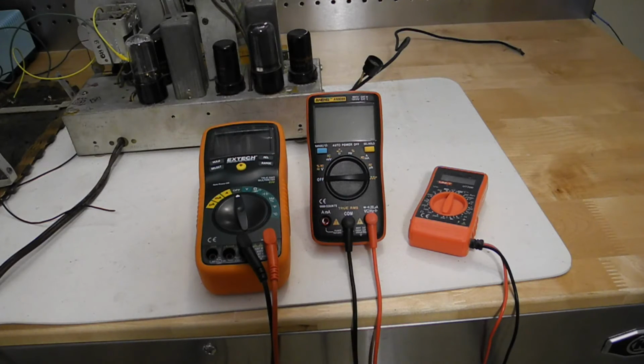Depending on the equipment, it may have significantly high DC voltages present. Check the rating on your DMM or meter and make sure not to exceed the maximum rated voltage. Most modern DMMs are rated to 500 volts or more, but some are not, and allow some margin of safety, as some DMMs may claim to meet CAT standards but may not actually have been approved.